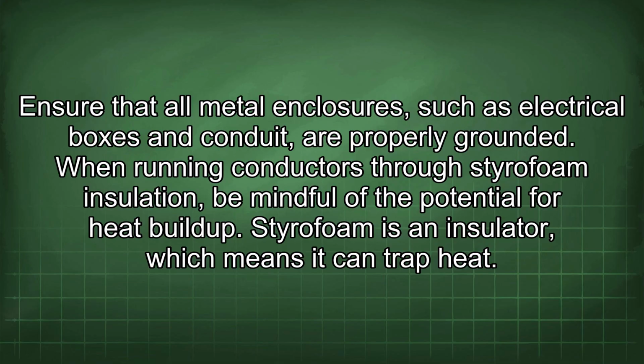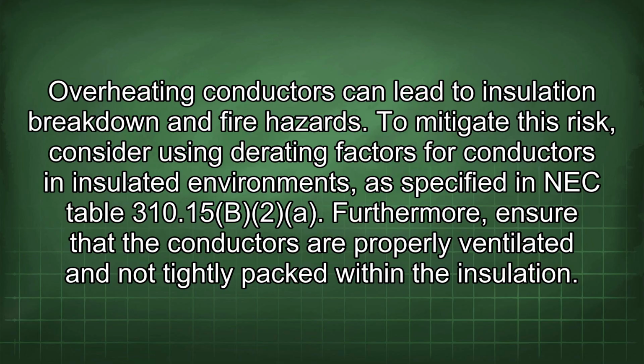When running conductors through styrofoam insulation, be mindful of the potential for heat buildup. Styrofoam is an insulator, which means it can trap heat. Overheating conductors can lead to insulation breakdown and fire hazards. To mitigate this risk, consider using derating factors for conductors in insulated environments, as specified in NEC Table 310.15(B)(2)(a). Furthermore, ensure that the conductors are properly ventilated and not tightly packed within the insulation.